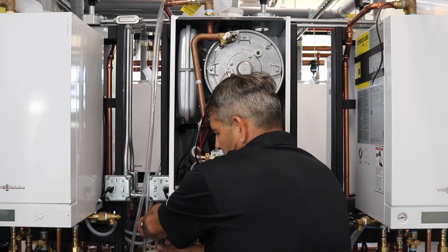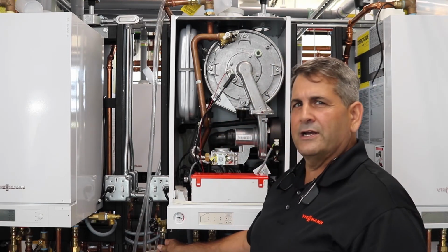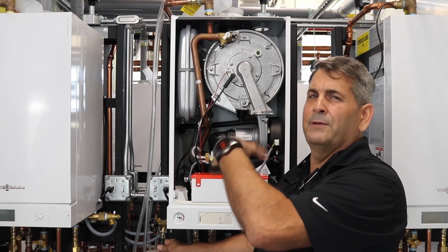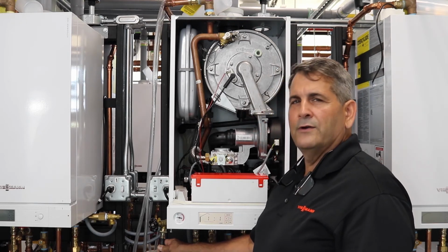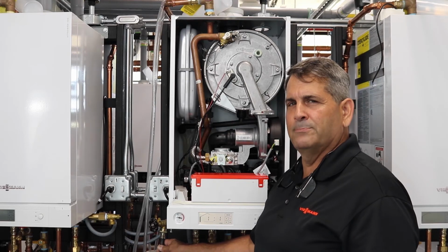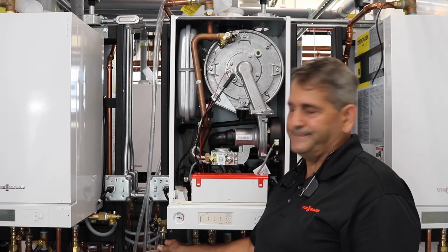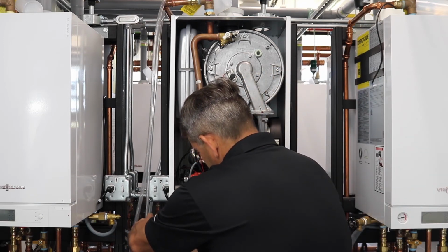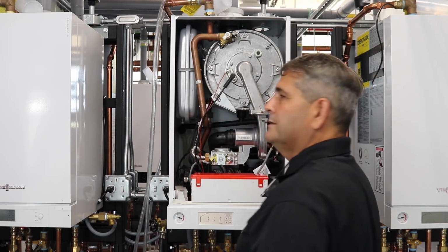So now we'll open up our purge valve. You'll hear the air come out, you'll hear bubbles, but you shouldn't hear water going through your system. That means you have air in your system. What I found when I was first putting these in, it takes about 4 gallons completely to get these completely air free. All right, it sounds pretty quiet now.